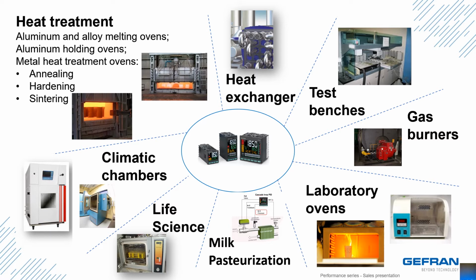Laboratory ovens are useful in small production areas such as ceramics, glass, gold, or dental products. Usually they require precise heating and cool down. Many times basic logic sequences need to be in place, such as door closed. Consider the energy calculation in applications for oven efficiency. Gas burners. Gas burner applications, a single Performance series can manage the burner system. It can be used with or without slide wire feedback and can display the motorized valve position on the face of the controller.